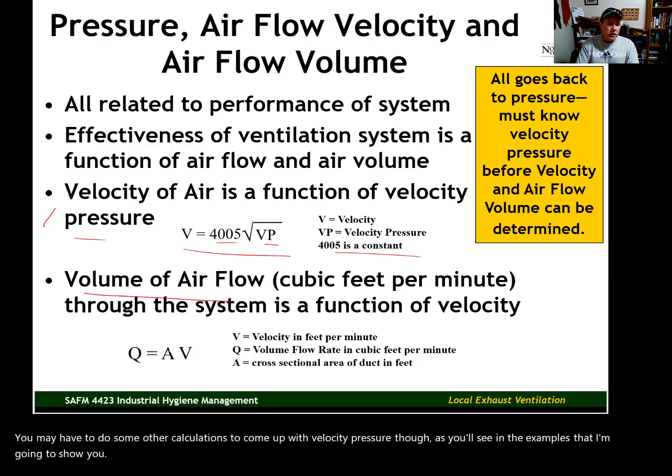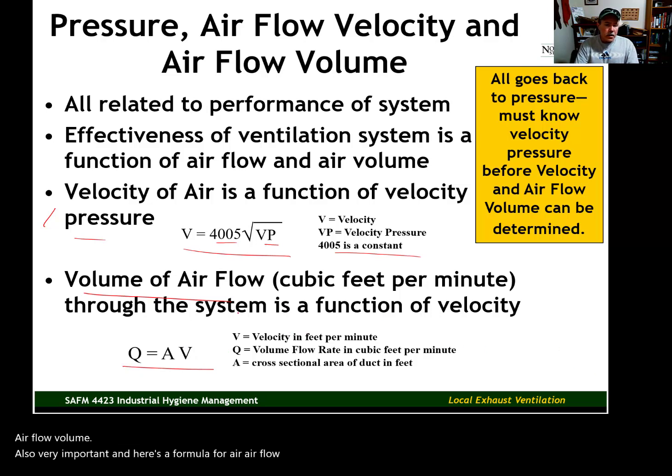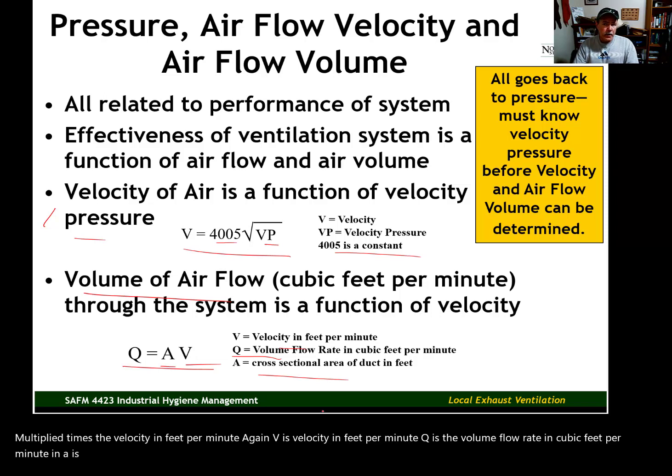Airflow volume, also very important. And here's the formula for airflow volume. Q equals area of the ductwork multiplied times the velocity in feet per minute. V is velocity in feet per minute. Q is the volume flow rate in cubic feet per minute. And A is the cross-sectional area of the duct.